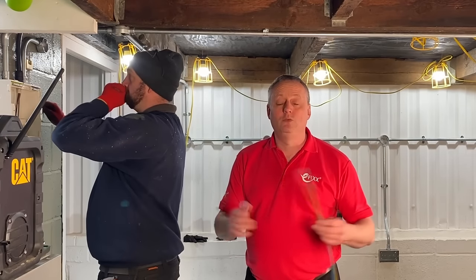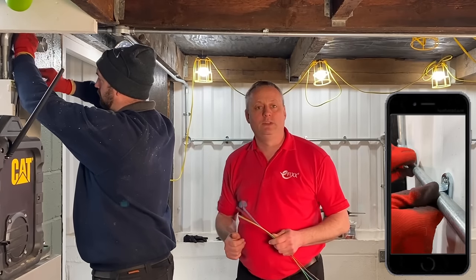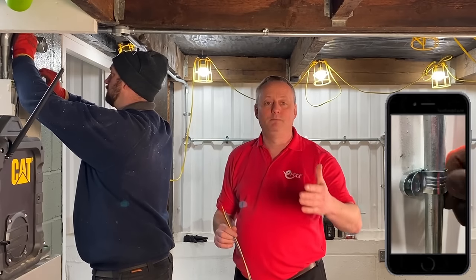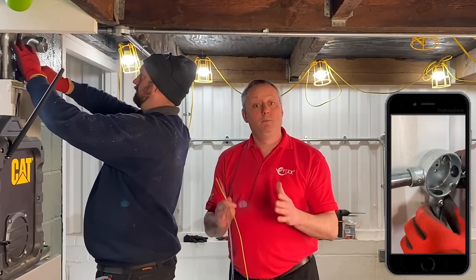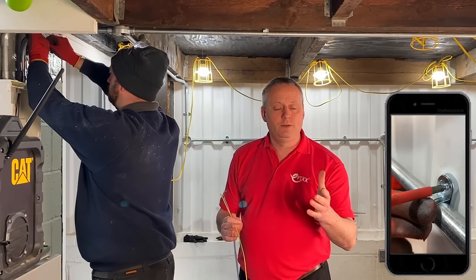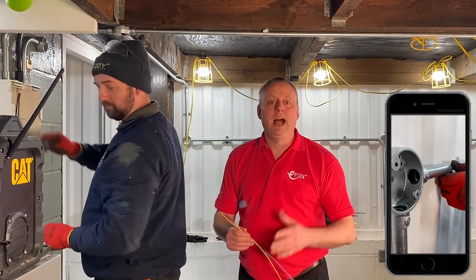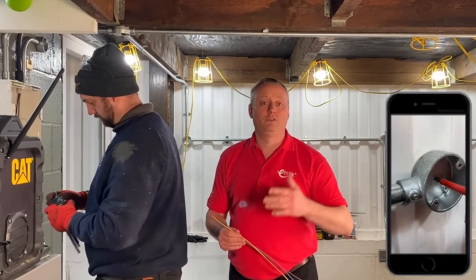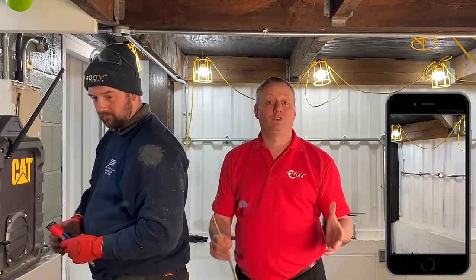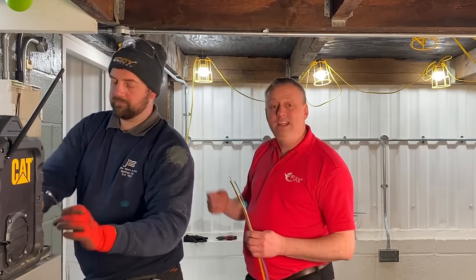In this video we're going to wire in PVC singles into the conduit system we've installed behind us. It was actually Rick that installed that system. If you haven't checked out that video, it's worth going to have a look because it uses a different method of connecting to spouted boxes and couplers — they use the Conlock system from Metpro where you just insert the conduit into the box and tighten down the grub screw. If you're more of a traditionalist who likes to thread, bend and set conduit, me and the Conduit King Jake Hardcastle have made a full playlist on that — I'll leave a link in the description.